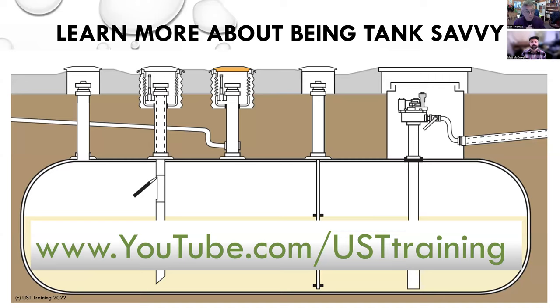So first off, you have to satisfy whatever jurisdiction you're in. It is largely looking at the tank top pads. And so you're checking all these openings to make sure that there's no problem there. You're also checking the condition of your automatic tank gauge. So it's pretty much limited to the tank top and the tank gauge. Maybe some states do require you check at your dispenser or underneath your dispenser. So, think about it as things that are readily easy to inspect. And you may even have to open up your containment sump lid if you don't have a sump sensor in there, because there's no way to tell if there's a leak in there. So it's tank top inspections.